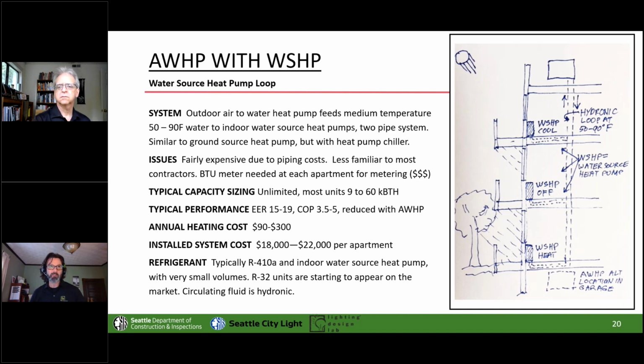And there are some free cooling options in some of the air to water heat pumps, free cooling, where it doesn't use the compressor to still provide a cooling effect when the temperatures are right. It's compelling. On a high-rise building, it's extra compelling if you can't do the refrigeration lift. And as you'll see in slides later on, when we really talk about getting rid of R410A, this is going to be one of the solutions out of that.